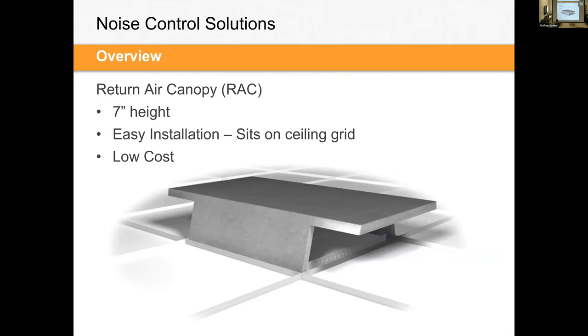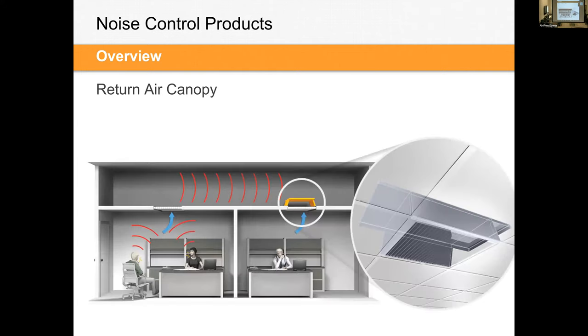The final type of air transfer, which is really one of the most common that we see and works extremely well, is a return air canopy or a RAC. And as you can see, it's basically a canopy over top of a T-bar ceiling grid open return. One of the added benefits that we hear, pardon the pun, and see a lot is that these completely block out the otherwise very open free area of those return grills.